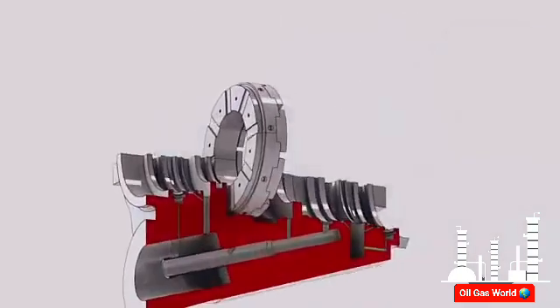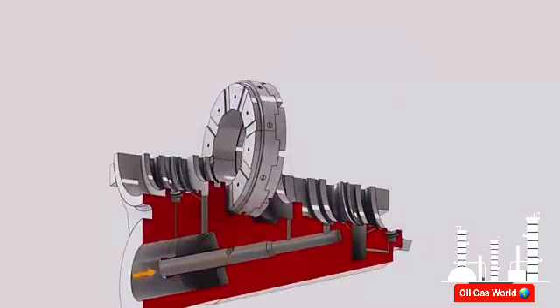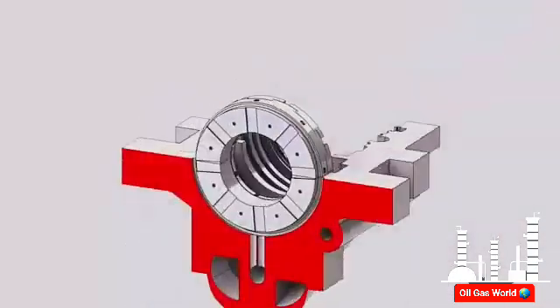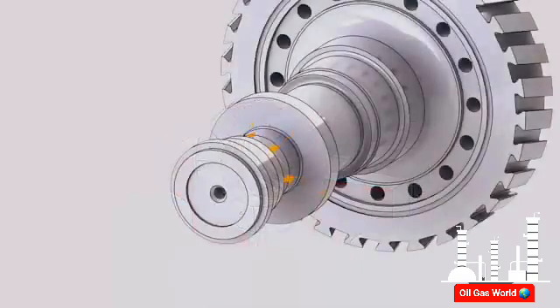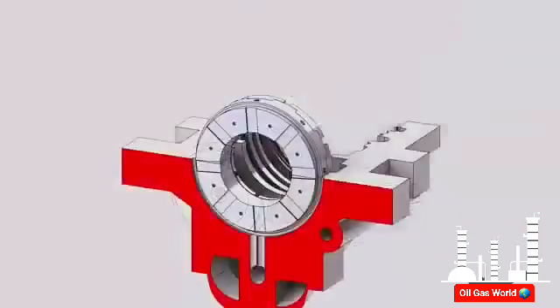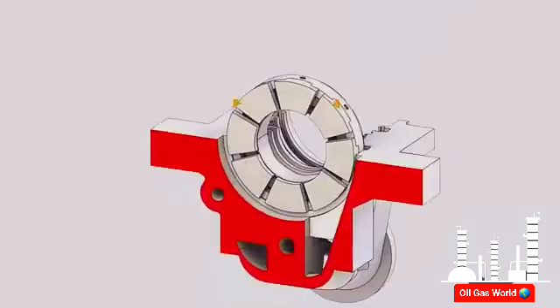For lubrication, oil is supplied through the oil feed pipe to two ports in the lower bearing housing, where the oil flows into annular space around the base ring. Then oil flows through grooves machined on the back side of the base ring to the bearing cavity, where it is carried by the pumping action of the thrust runner to the entire bearing surfaces. Oil exits at the pad's periphery to the thrust bearing drain cavity, down to the lube oil drain piping.